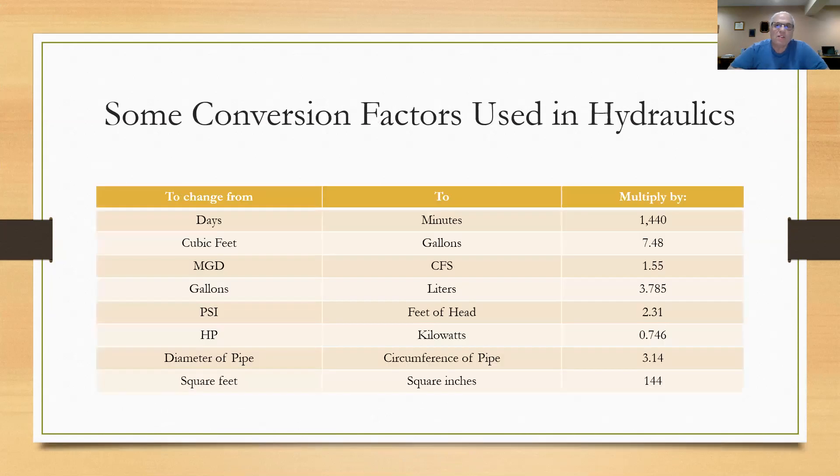Here's some conversion factors that you use in hydraulics. In this table, you'll see this on all of the slides that I produce for the hydraulic series. For example, if I wanted to change days to minutes, I would multiply the days by 1,440. If I wanted to change PSI to feet of head, I'd multiply by 2.31.